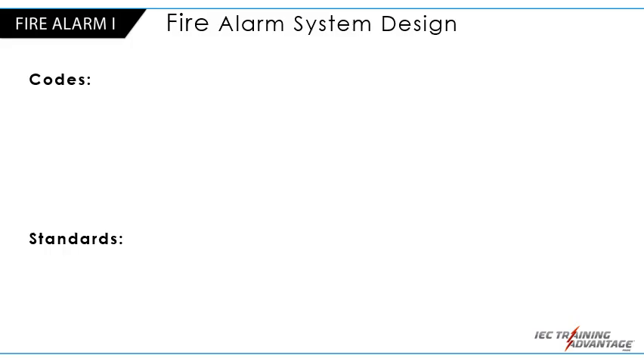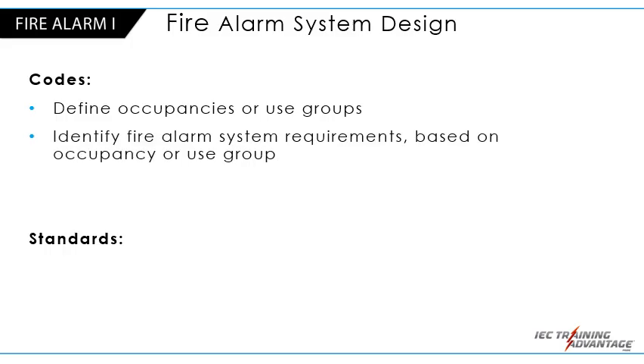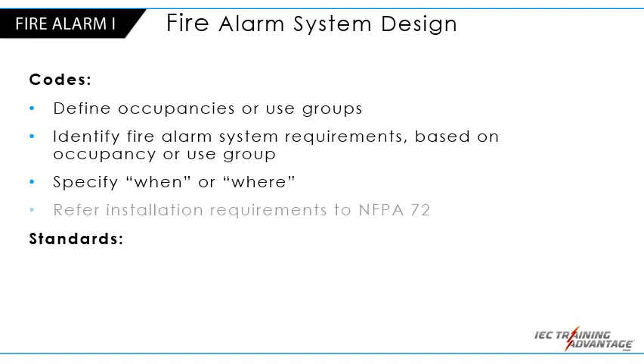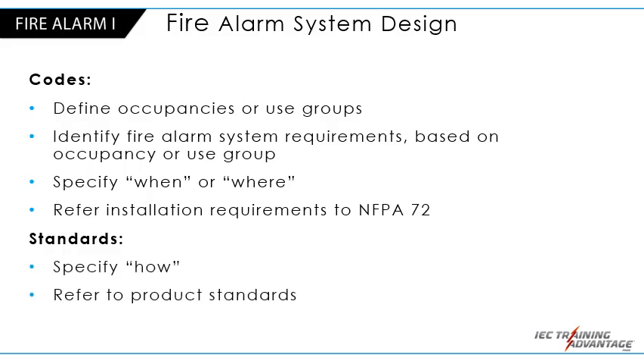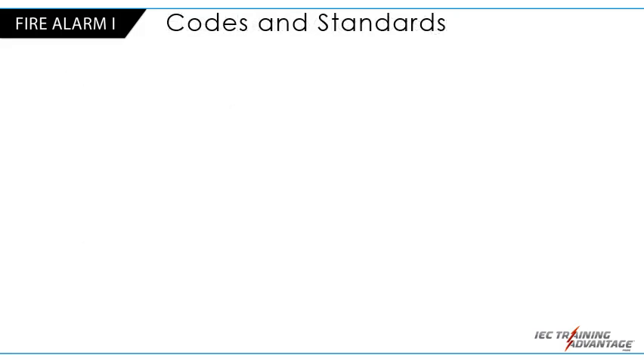For codes, they define occupancies or use groups. Codes identify fire alarm system requirements based on occupancy or use group. Codes specify when or where, and codes refer installation requirements to NFPA 72, whereas standards specify how, and standards refer to product standards. Codes indicate the type of system required, whereas standards specify how systems are installed.